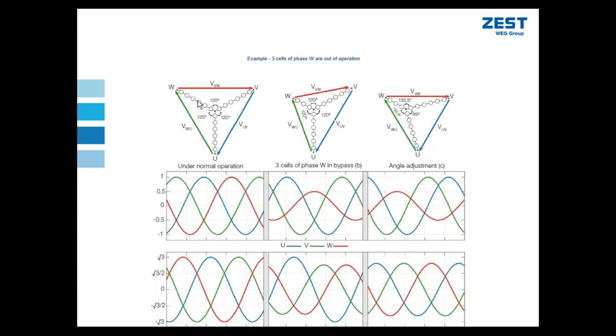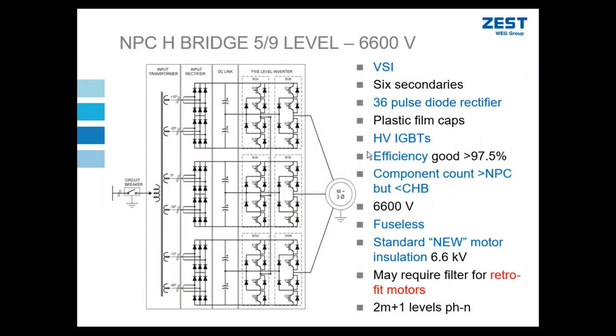but instead of reducing the amplitude of the voltage output in the other two phases to find balance, what you do is, again, because we are in control of the algorithms of firing the voltage output to the motor, we make some adjustments to the phase angle between the three phases in order to balance the phases with a very limited reduction in output voltage. Okay, that's the end of our discussion on H-cell multi-level inverters.